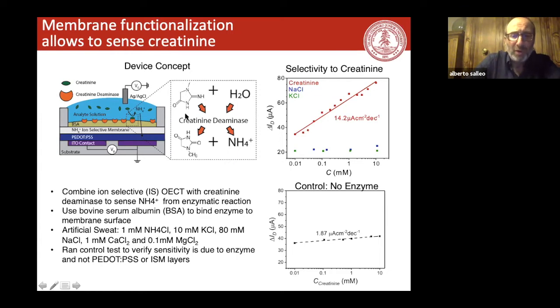Now you wonder whether the ammonia itself would be an interferent. And it turns out that it actually isn't a big interferent because this BSA actually creates a barrier for the ammonia that comes from the solution into the membrane. So you really are more sensitive to creatinine than to ammonia. So ammonia interferes a bit, but if you had an ammonium sensor nearby, you would be able to subtract the ammonium signal from the creatinine signal and actually get the creatinine signal.